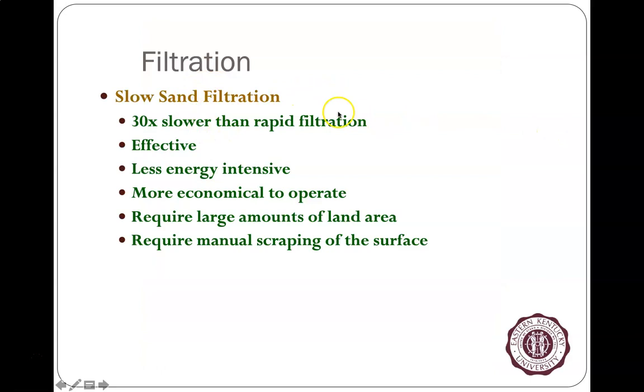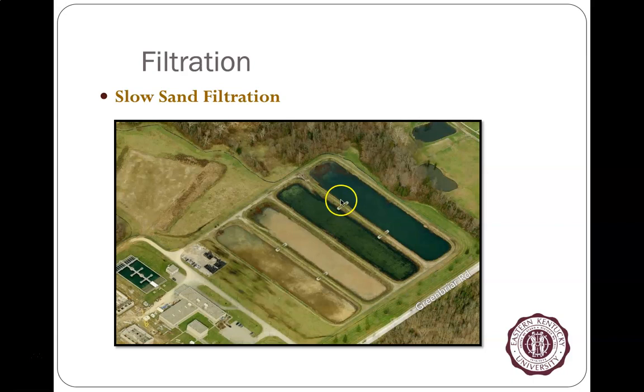Another method is slow sand filtration. Some communities that have a lot of flat land may use it. It is 30 times slower than rapid filtration. It is effective, doesn't require as much energy or power, and can be more economical to operate, but you have to have large amounts of land area, and you have to scrape the surface periodically.